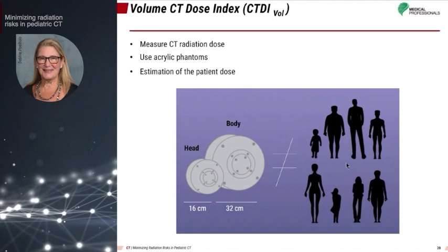The volume CTDI is displayed on the scanner console before each exam and reported in the data page or DICOM structured report. It is crucial to check the planned volume CTDI before proceeding with the acquisition to ensure that the scanner output is adequate for the child.